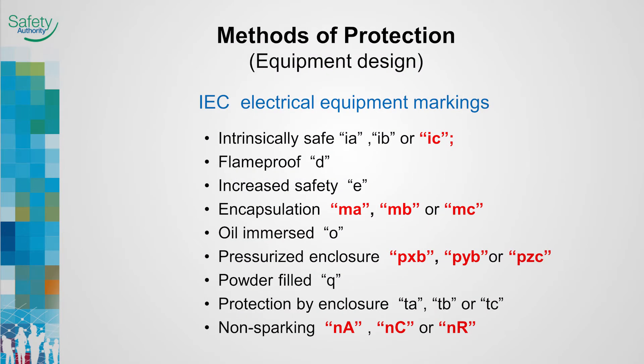New additional methods of protection are shown in red. Equipment may be marked with methods of protection which indicate the specific type or types of design incorporated into a device or equipment instead of an EPL. When this is the case, the user must consult the code to determine the suitability of the equipment design for the intended application within the explosive gas or dust atmospheres.